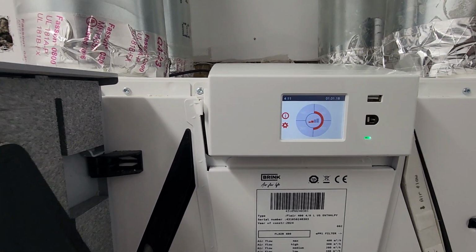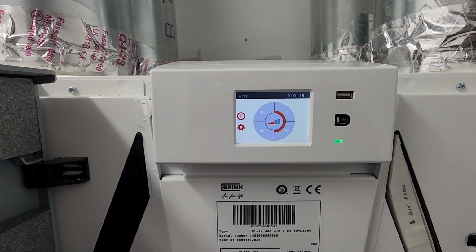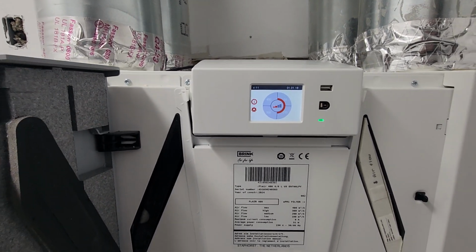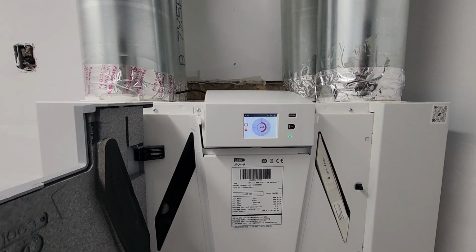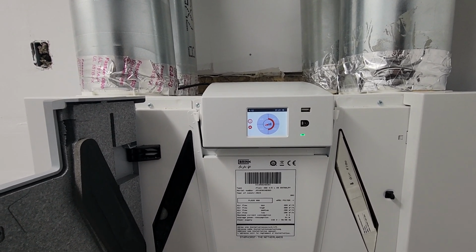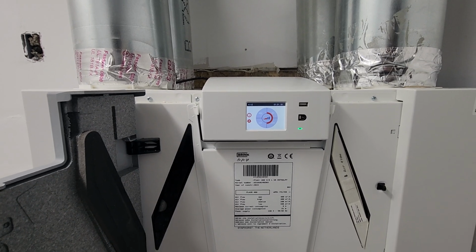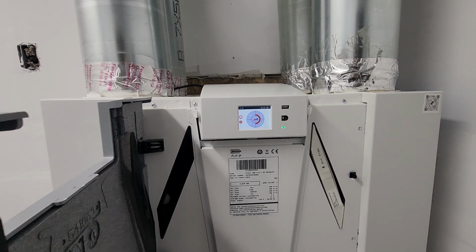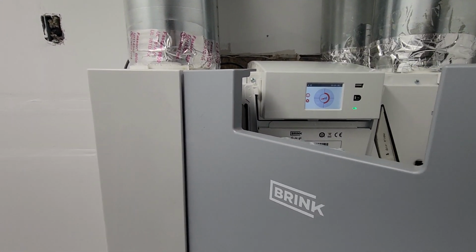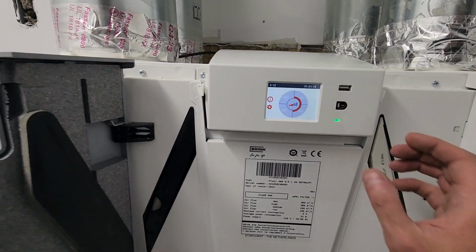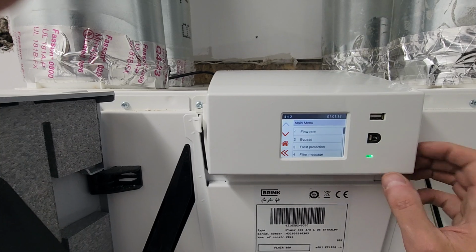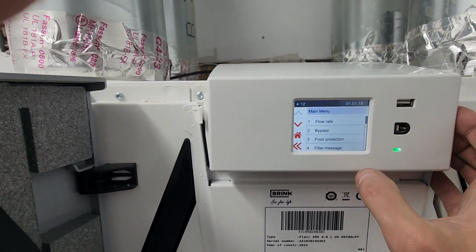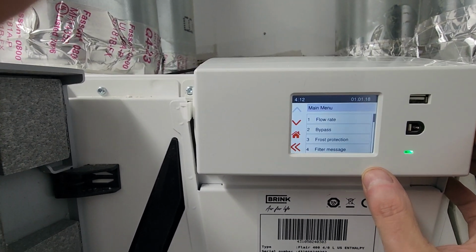And right now it's set at 255 cubic meters per hour. Was that in CFM? I think we're around 140-ish or so CFM that we're exchanging. And then we can boost up probably near 200 or so, maybe even a little bit more than 200 CFM when we go into boost mode. So pretty cool unit. It's easy to program. It's easy to change your individual flow rates. It's easy to put on and change frost protection, other things like that.